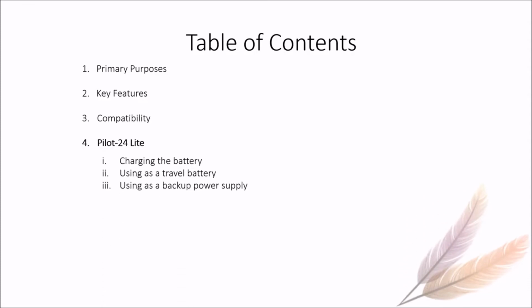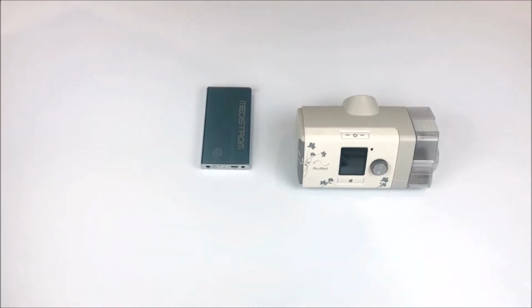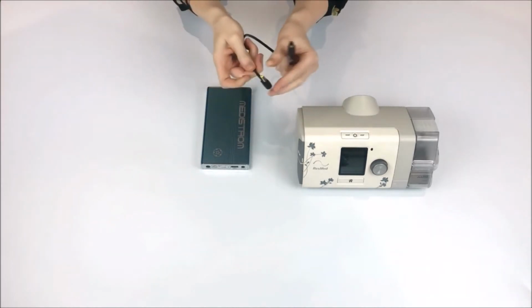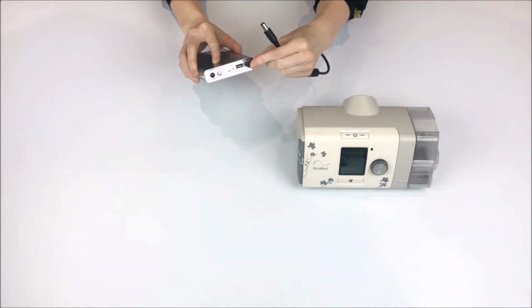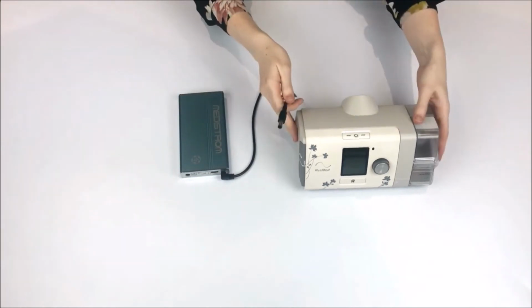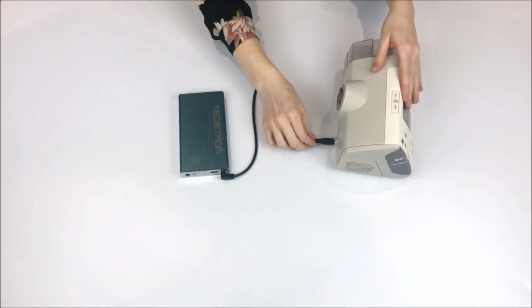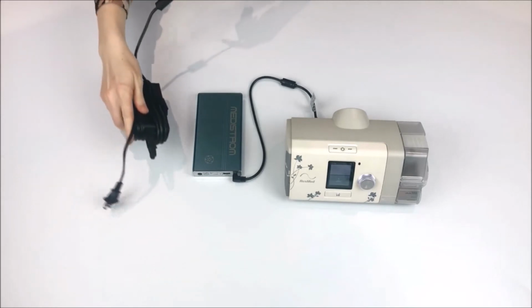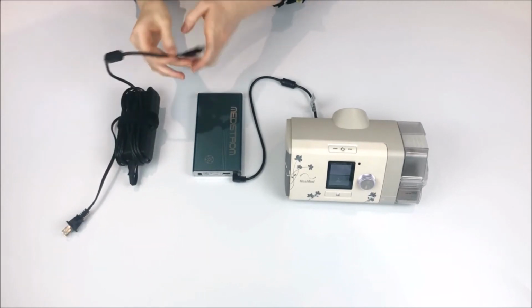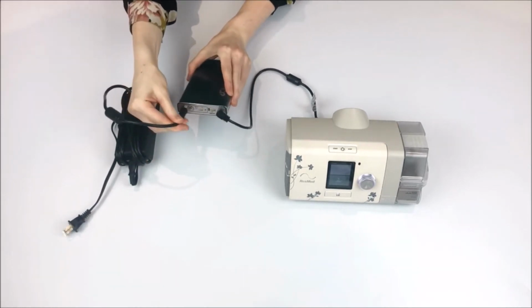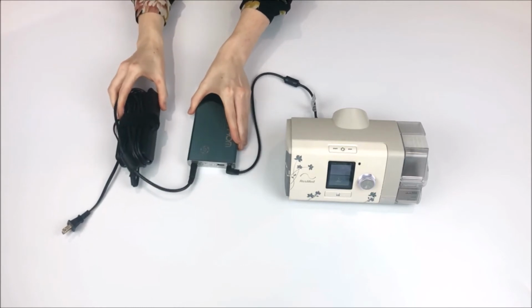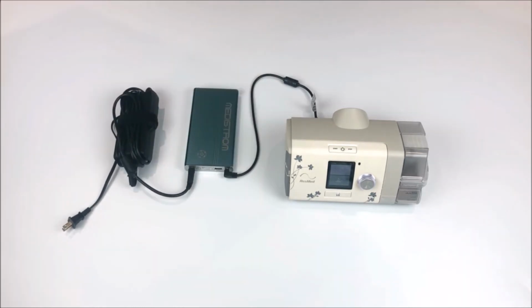When using as a backup power supply, you will set up the battery so that it is in line between the main power supply and the CPAP machine. Starting with the AirSense 10, we'll connect the battery to the machine using the DC cable. You will then take the AirSense 10 power cord to connect the battery to the wall outlet. Now if the main power goes out, the battery will provide power to the CPAP machine seamlessly.